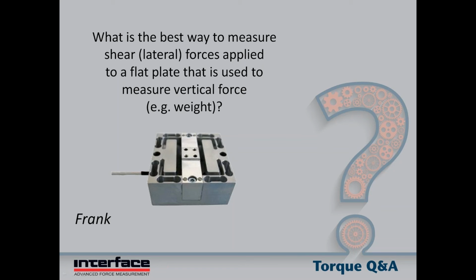Good answer, Chris. I guess one last point on that is I've had some customers who don't really trust shrink discs because they can slip, and when torqued to their specification, they will not slip, but the specifications also require that there not be grease on the shafts, be clean and that kind of thing. And in some cases, if there's a test specimen that wants to be changed in and out a lot, in practice, you can't necessarily guarantee that technicians are always going to torque everything to spec and everything like that. So in some cases, the keyed coupling can allow, say, quicker or more assured assembly without slippage, but you have the trade-offs of that we've mentioned previously.